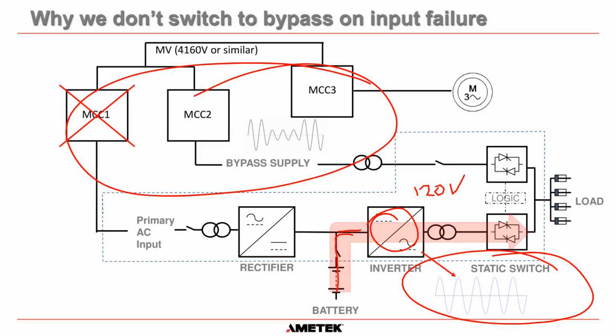And that is down to how long the designer of the system designed the battery. It could be anywhere between 1 to 3 hours for most process control UPSs. But it is not going to be affected at all by all the disruption that's going on in the plant. So these loads here are going to get a beautiful sine wave and carry on regardless when the plant is in such an unstable state.